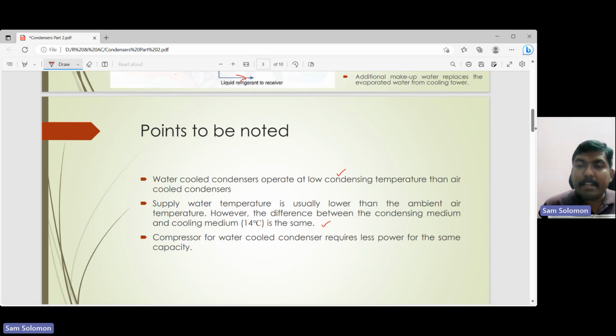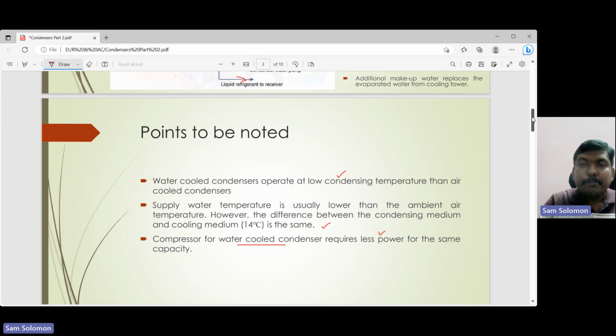And one advantage is that the compressor which we use in a system where a water cooled condenser is used requires less power for the same capacity. Because your water cooled condenser removes a large amount of heat and converts the refrigerant back into a refrigerant liquid, the power that is used for running the compressor is a little bit less when we use the water cooled condenser. Okay.